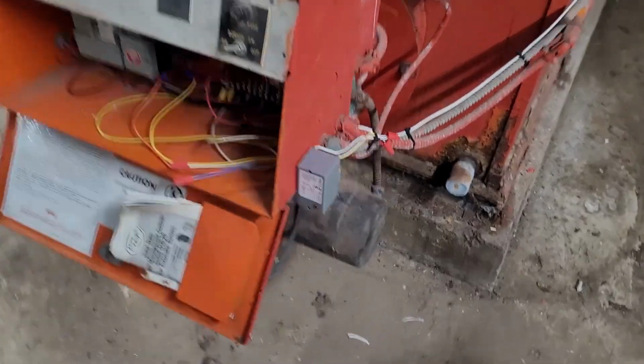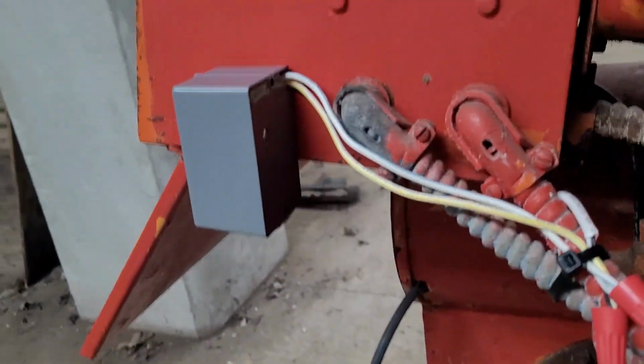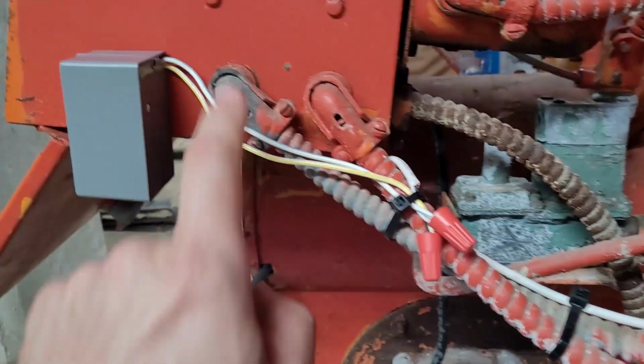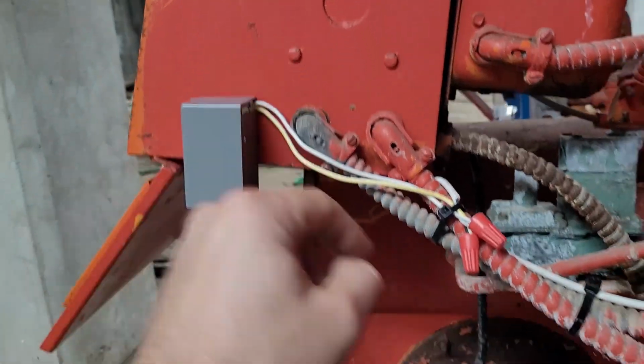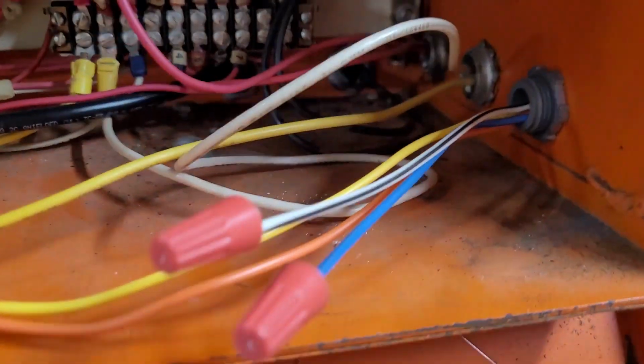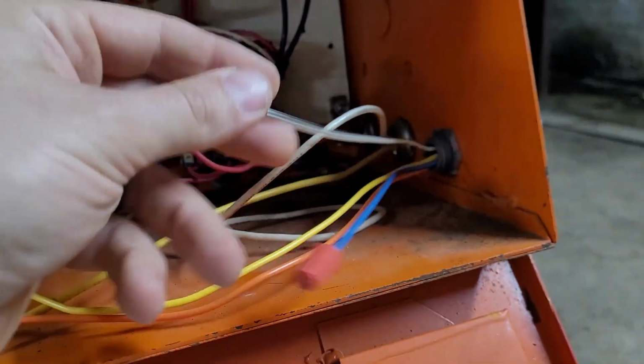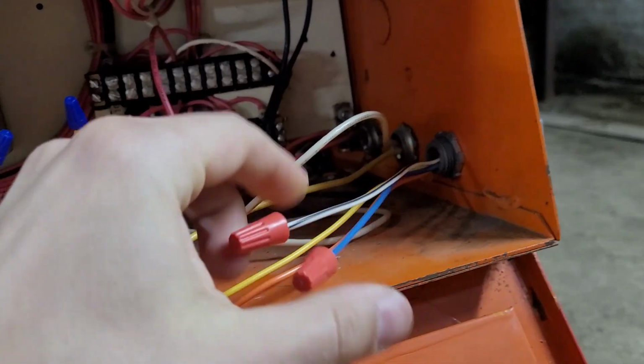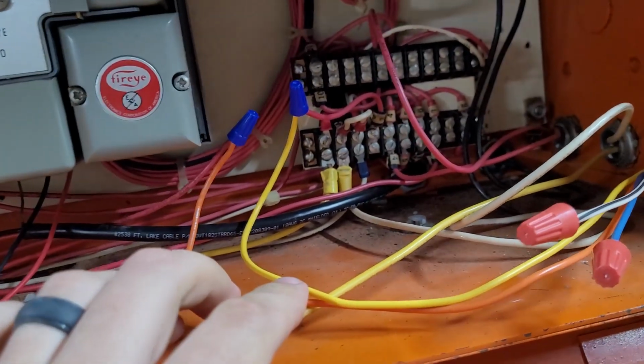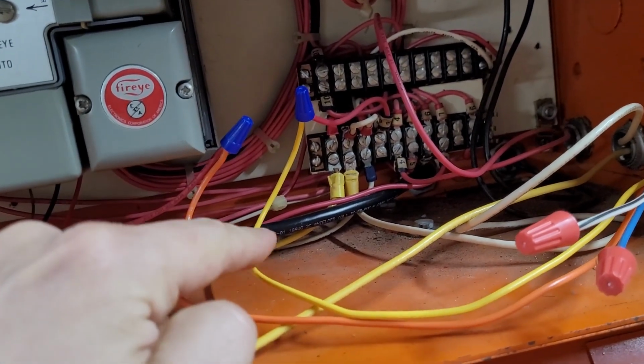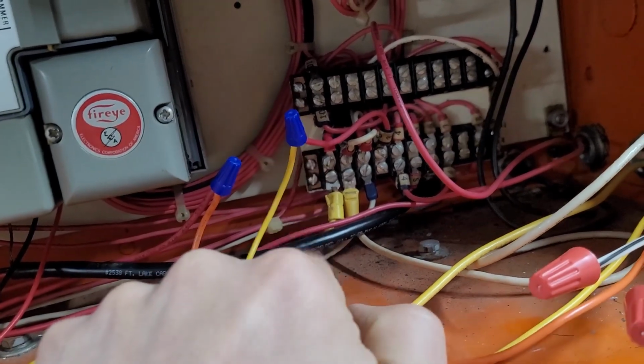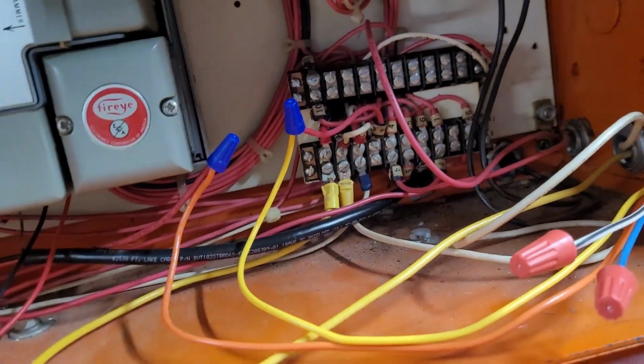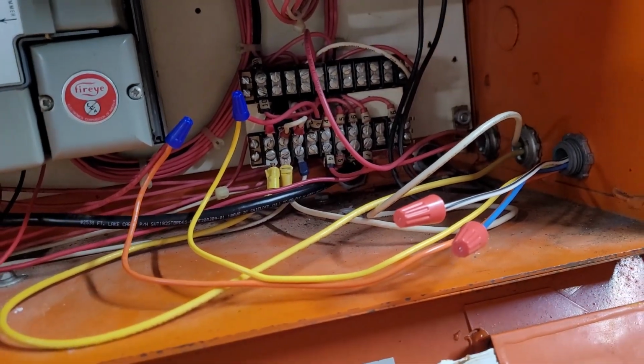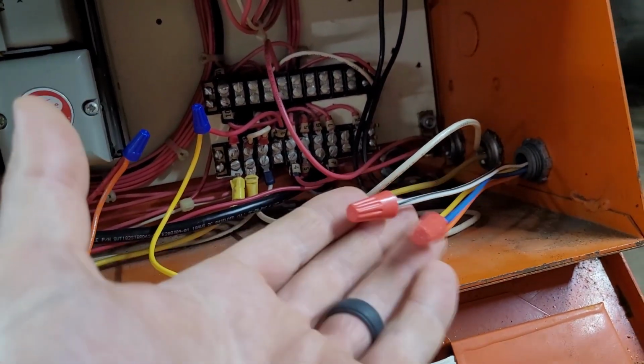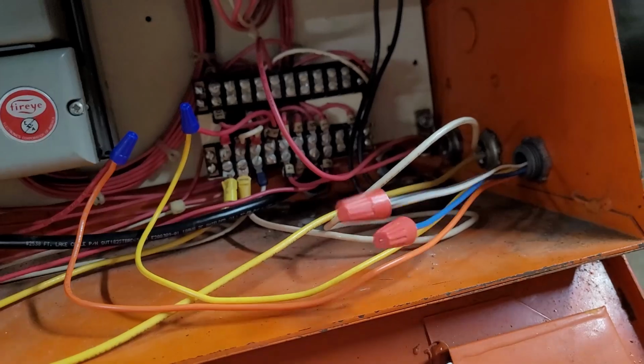Okay, so here it is installed. You got the low voltage popping out the back side of the relay, so that way we don't have to poke another hole in the side of the enclosure for the low voltage to come in. And then on the switching side of the relay, or all the high voltage stuff, so this is still the high voltage coil, but put that inside. But on the switching side, you've got the common and the normally open, and I've just cut that number 3 wire, put the relay in between, and then also very important, cap off any wires that are unused because they will at times carry voltage.